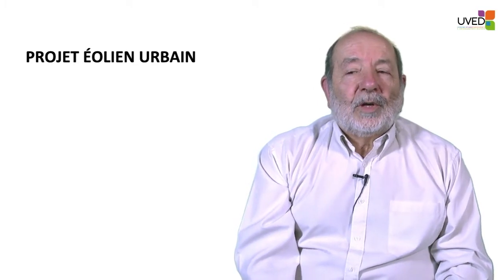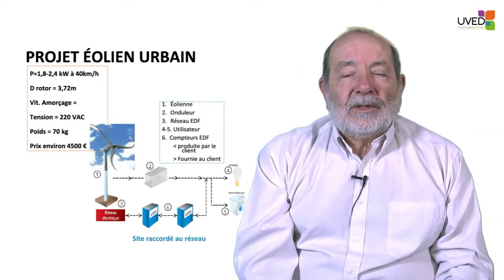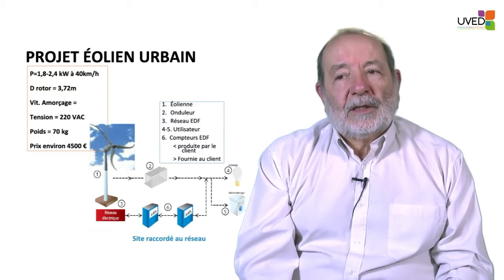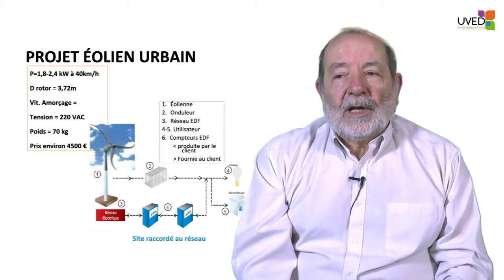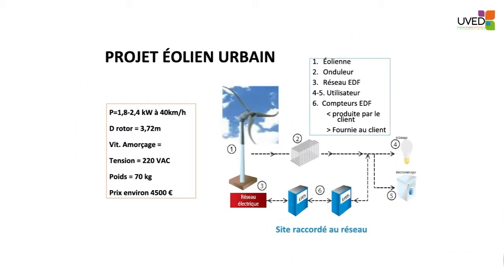If the site is connected to the grid, the energy recovered by the windmill is first rectified, sent through a DC bus, and then injected into the electric grid. When the windmill is not rotating, the user can draw power from the normal grid — which is why there are two different electrical power meters. Here we have a windmill producing between 1.8 and 2.4 kilowatts at 40 kilometers per hour with a rotor of almost four meters in diameter.